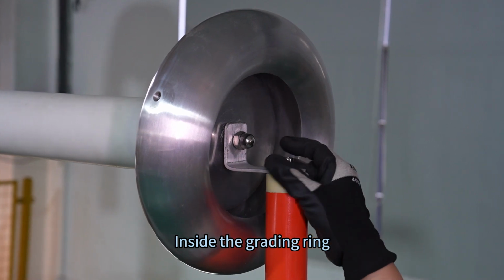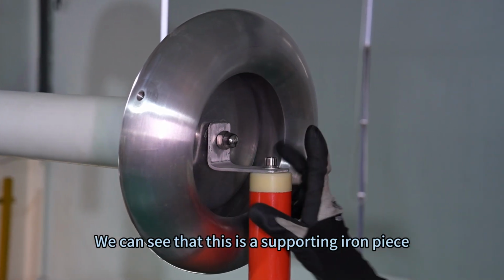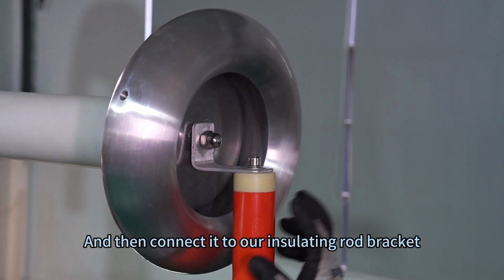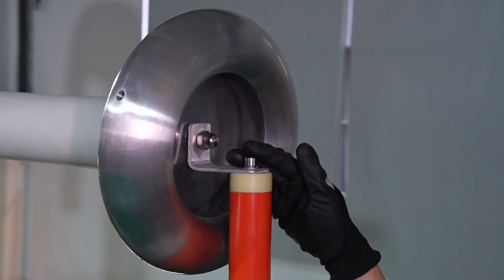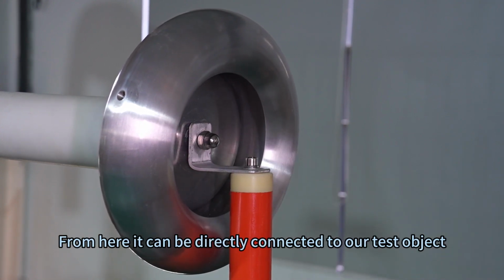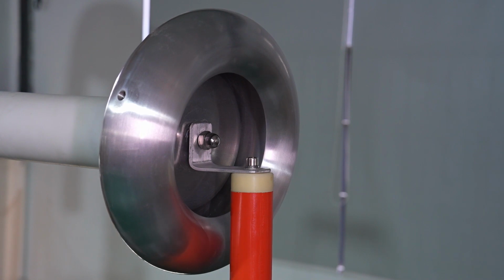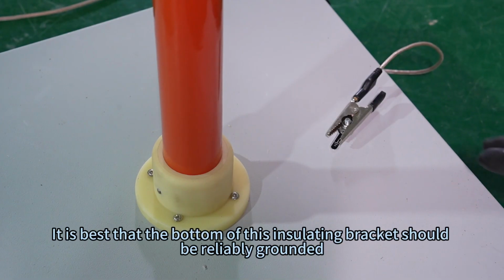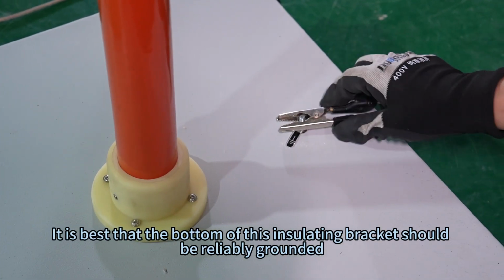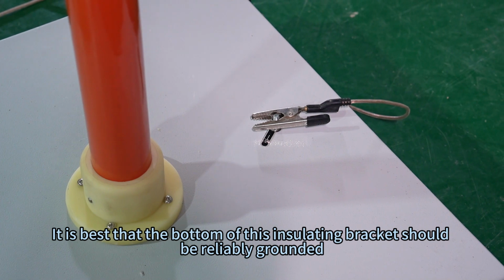Inside the grading ring, we can see that this is a supporting iron piece, and then connect it to our insulating rod bracket. From here, it can be directly connected to our test object. Then conduct an experiment. Give it a support, put it up. It is best that the bottom of this insulating bracket should be reliably grounded.